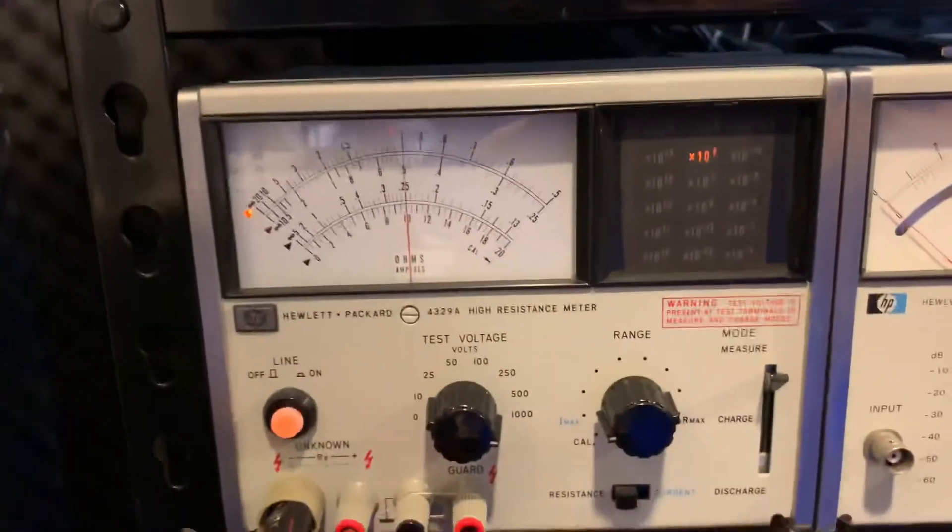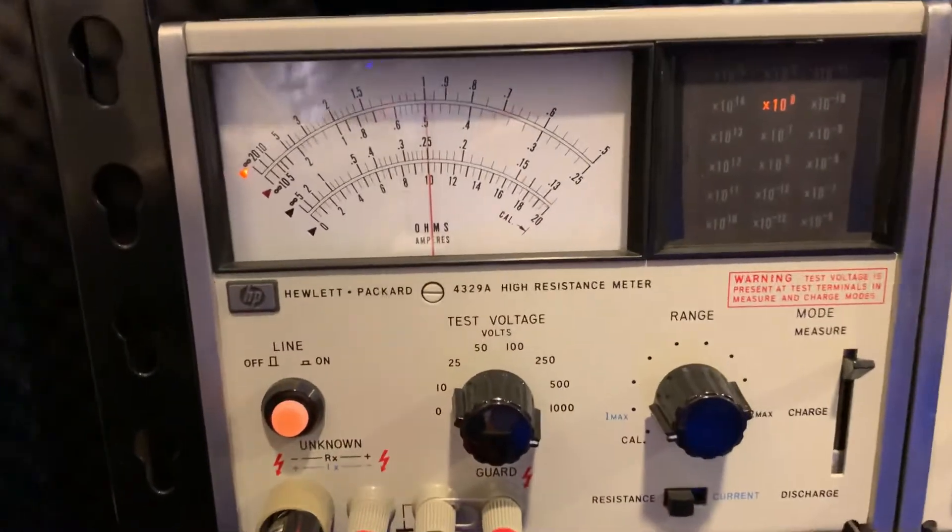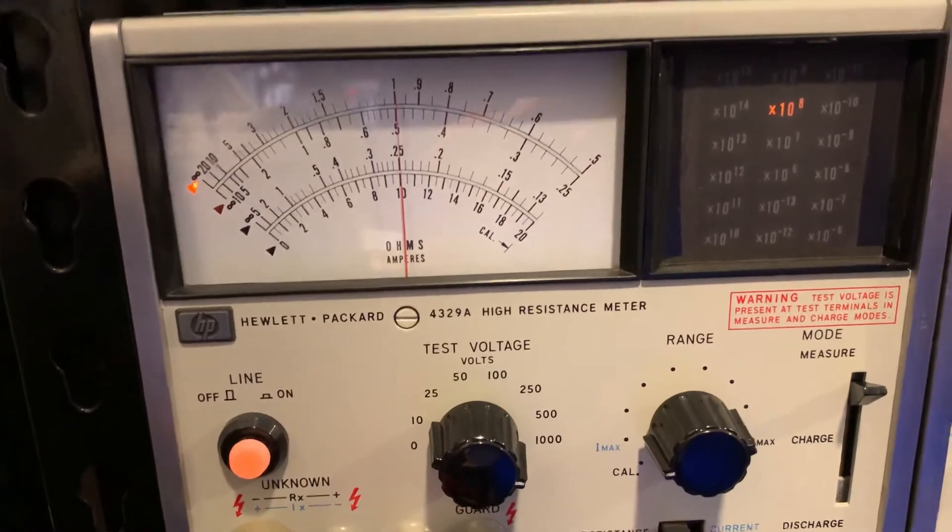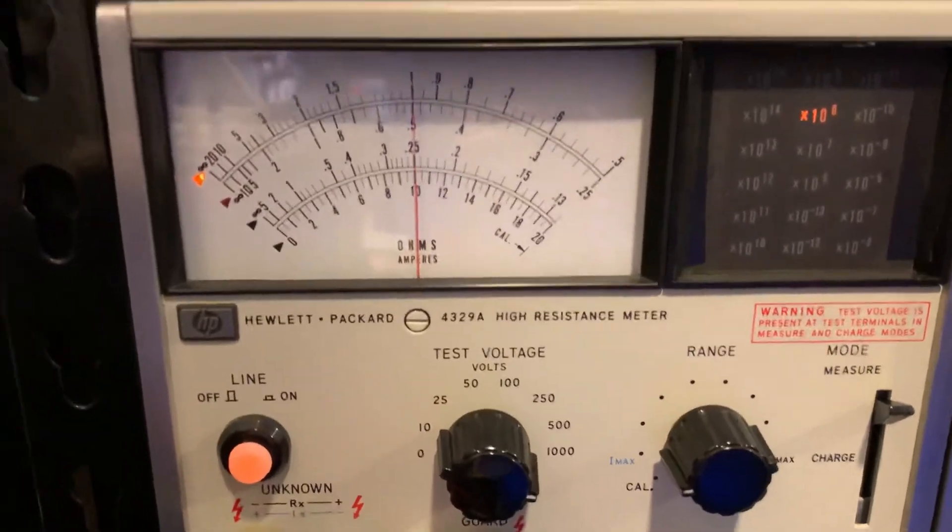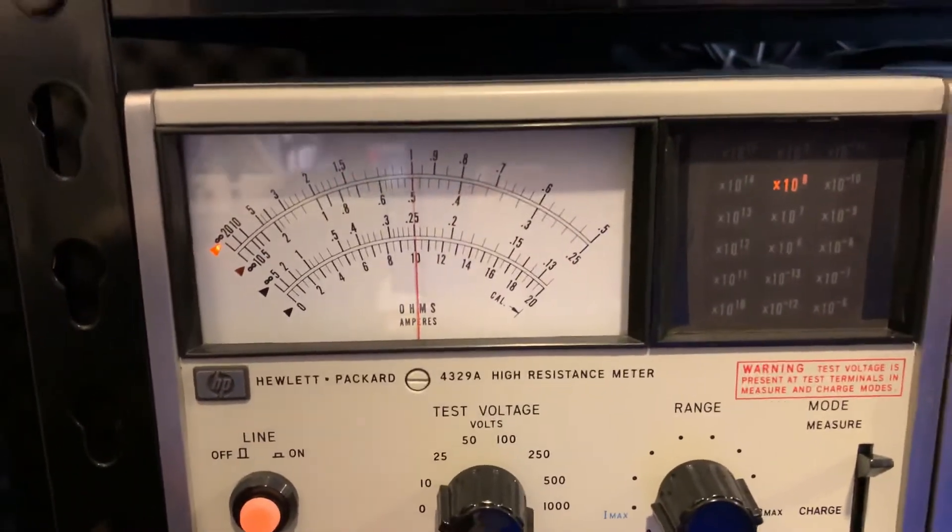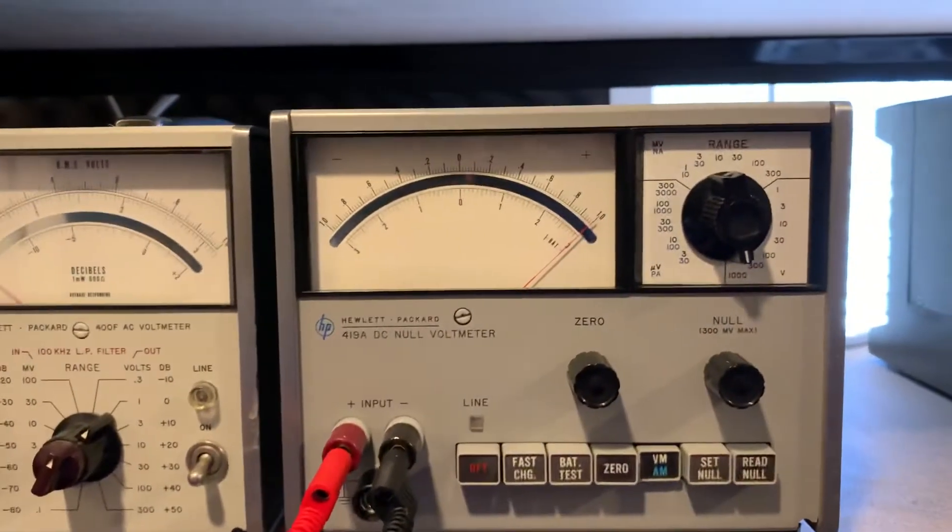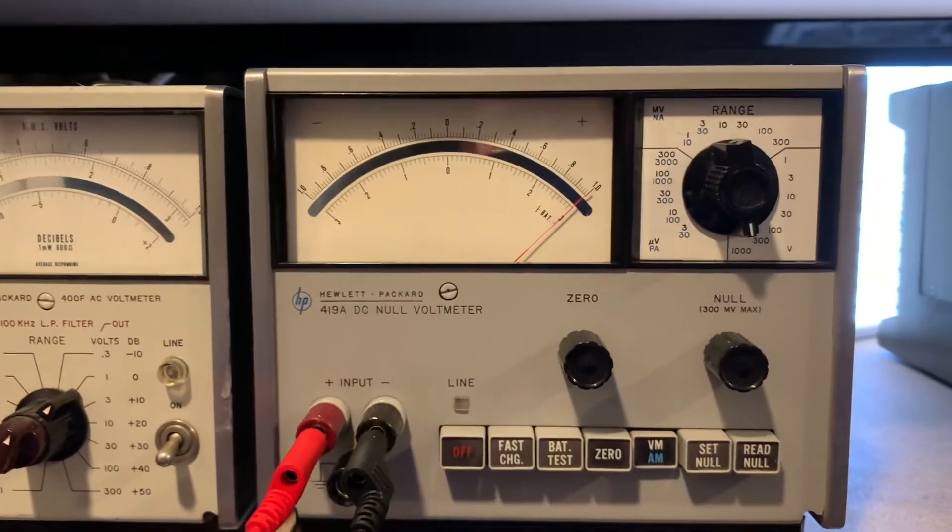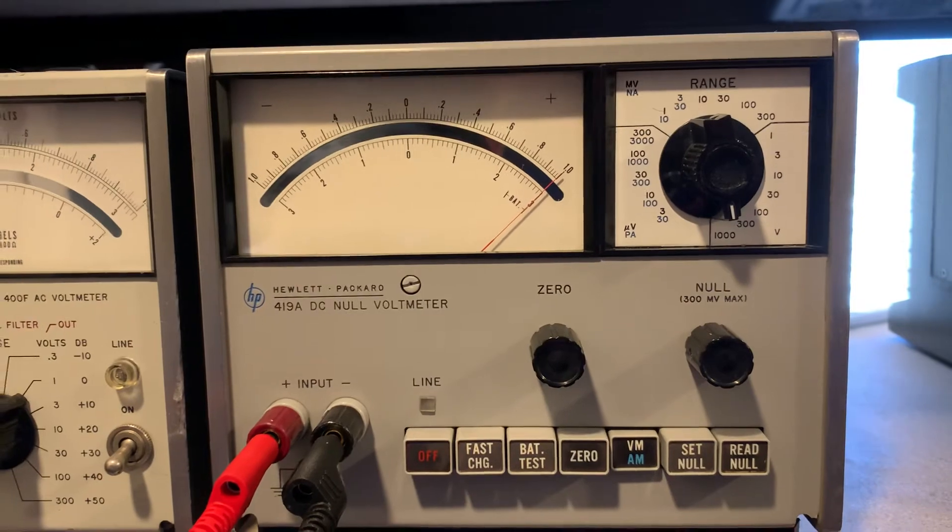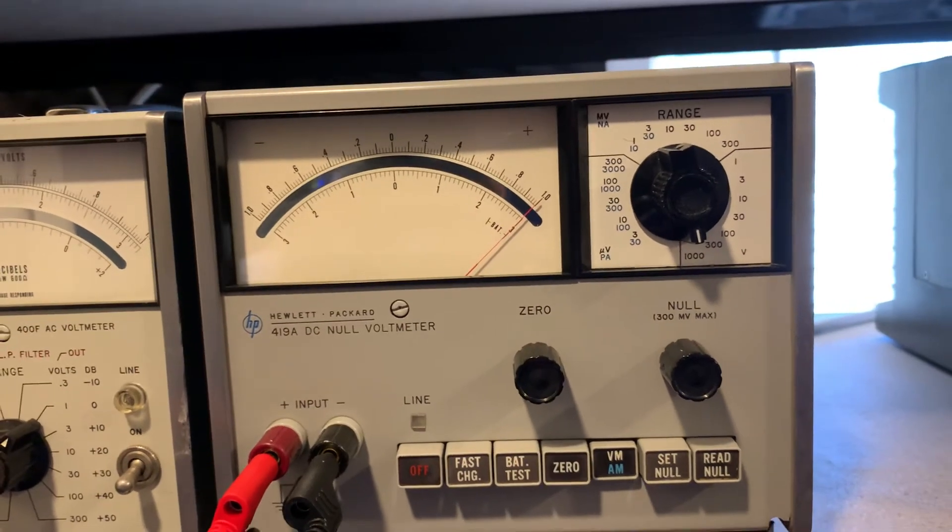Also, we're measuring the input impedance. So that's 1 times 10 to the 8th, that's 100 megohm. That's exactly what the input impedance, the HP specifies for the 419A, 100 megohms.